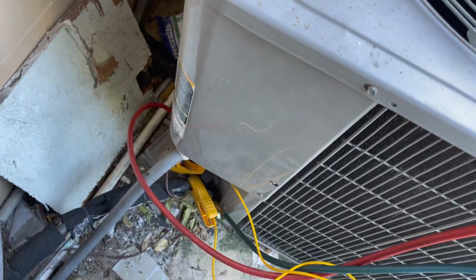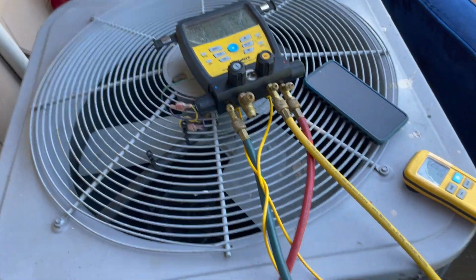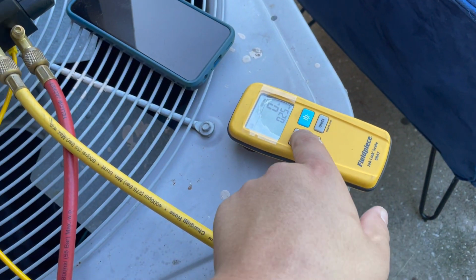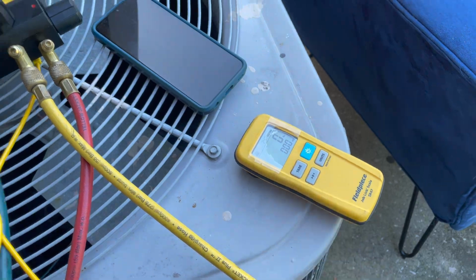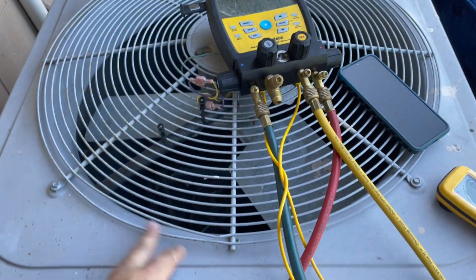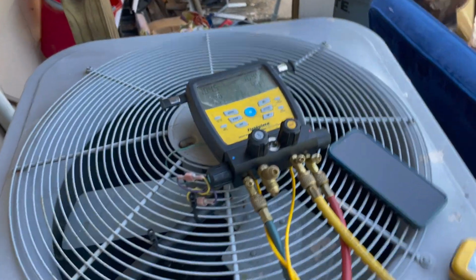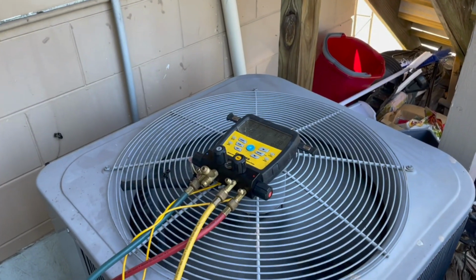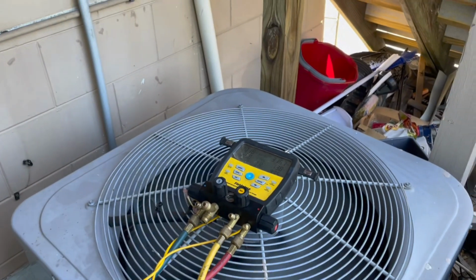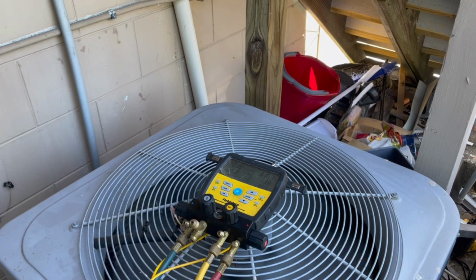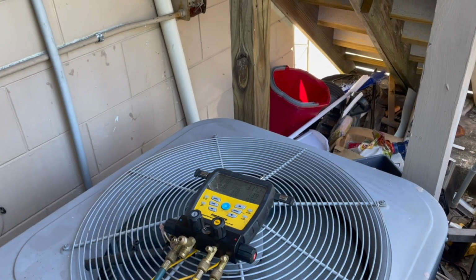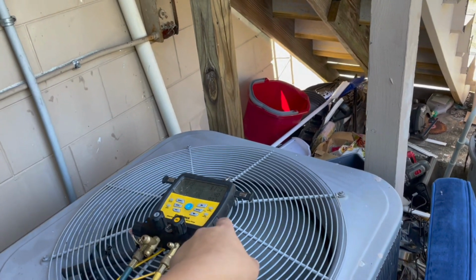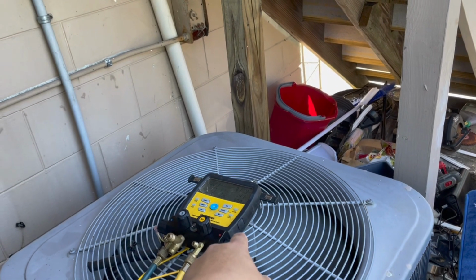So gauge is hooked up, everything's purged, tank scales zeroed out. There we go. So I'm gonna go turn this thing on, and then we'll come back and we'll start charging it up. Okay, so added 3.5 pounds. I'm watching the system run. My low side still doesn't look great. My high side looks a lot better, just at that 14 degrees of subcooling that the system wants.